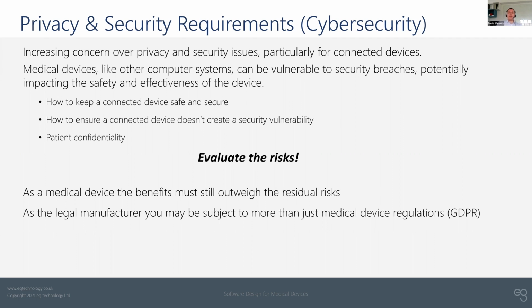If it provides something as simple as Bluetooth connectivity to an accessory, all of those are points of potential weakness. So you need to think very carefully about how to keep your device safe and secure, and of course, how to keep any patient data that's recorded appropriately confidential. Although 62304 doesn't deal specifically with data security from that aspect, things like GDPR and confidentiality do factor heavily in your design decisions.